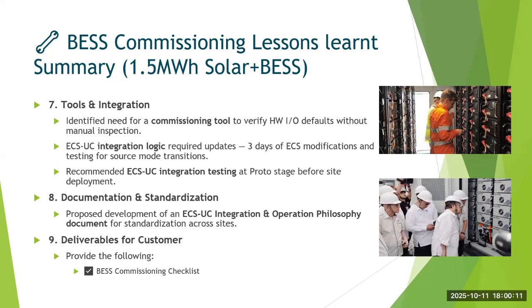What was happening is that the information between the EMS and the unit controller at the BESS level did not match; there was a difference in the variables. Because of this, when the EMS commanded charging, it was not charging at full capacity, because the scaling factor used in the unit controller was wrongly set. It should have been 0.1, but they initialized it to 0.01. Though the EMS was commanding, for example, 100 kilowatt, I was getting only 10 kilowatt. When we troubleshot, we saw that the EMS logic was correct, but the scaling factor parameter in the unit controller was wrong. So those things have to be tested with a simulation to check that everything is fine, so that we have a proper integration.